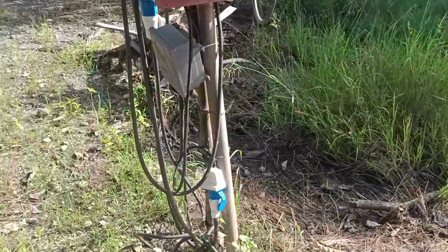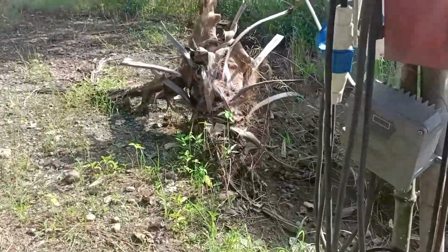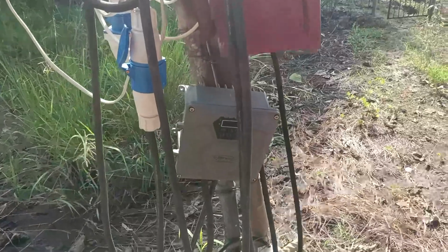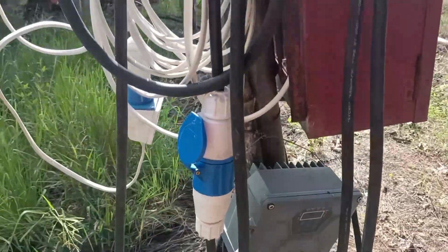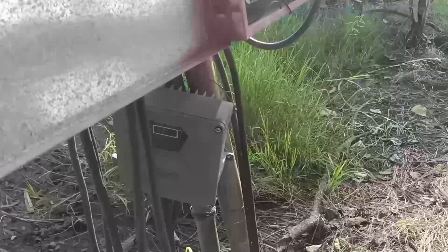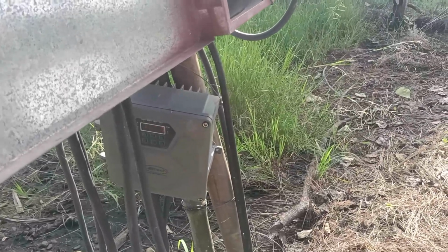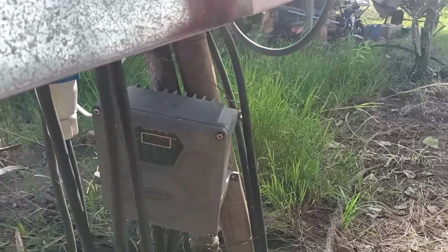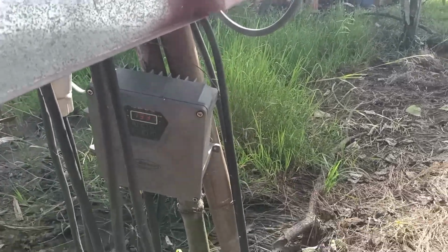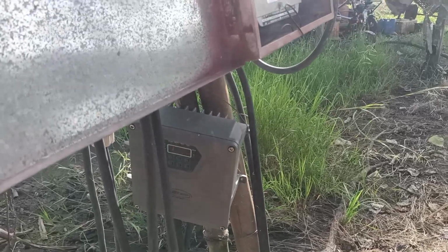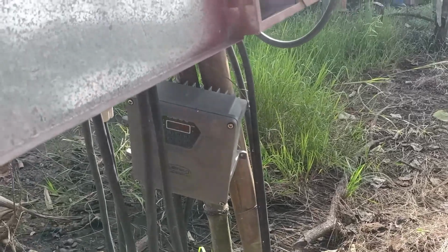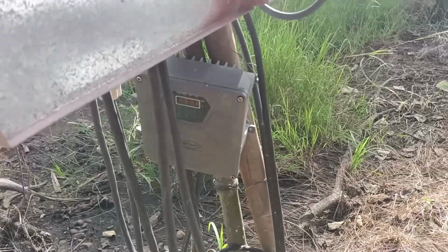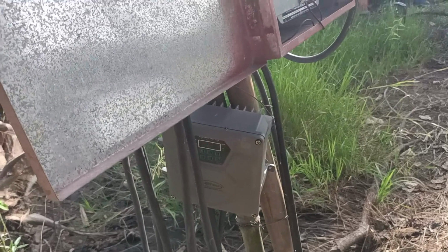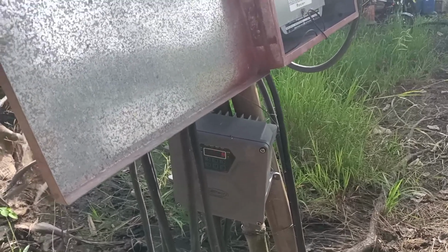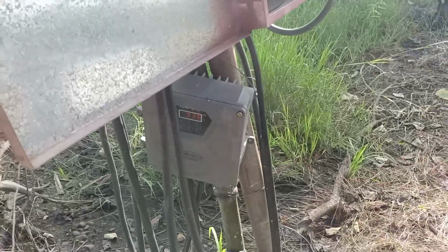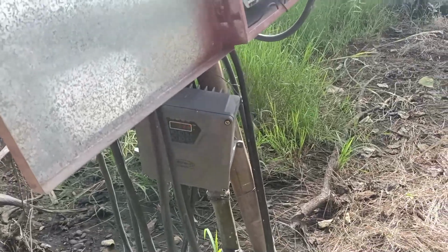So I'm going to do some tests using the solar connector, just to see what's going on. First, I'm going to turn on the submersible. The reading at the panel is 193 volts. However, it's out of calibration—add 10 volts to it, so it's actually 203 volt AC going into the control box.